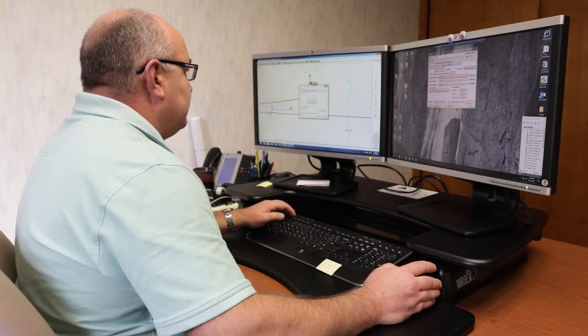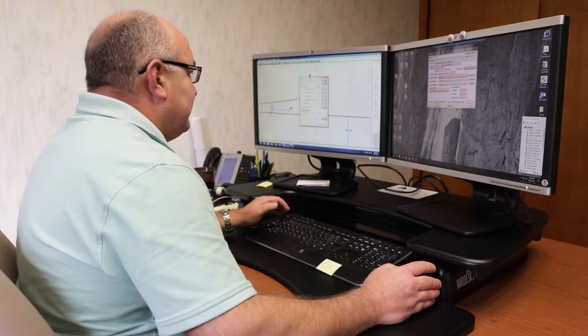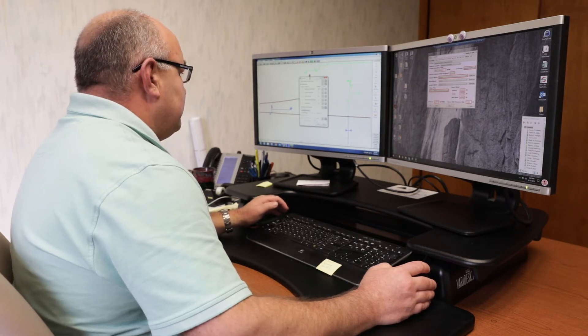Operations Analytics has been a great value to us in finding overloaded and underloaded transformers. We use it seasonally to find any transformers that are overloaded and underloaded. We also use it regularly to find and right-size transformers. It's a great asset for aggregating multiple meters on a transformer, and it gives us the ability to compare a facility to a similar site to right-size a transformer.